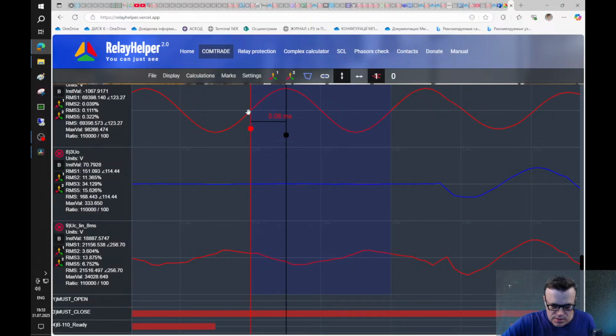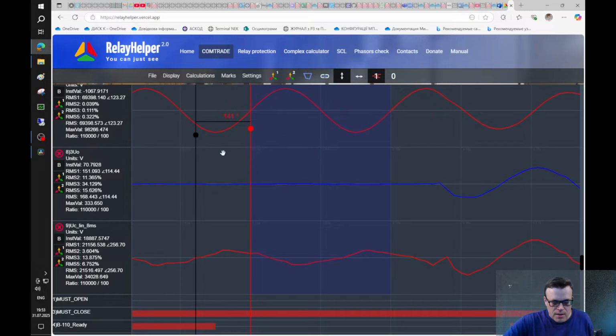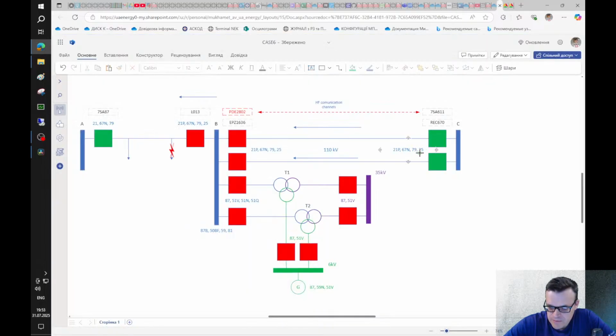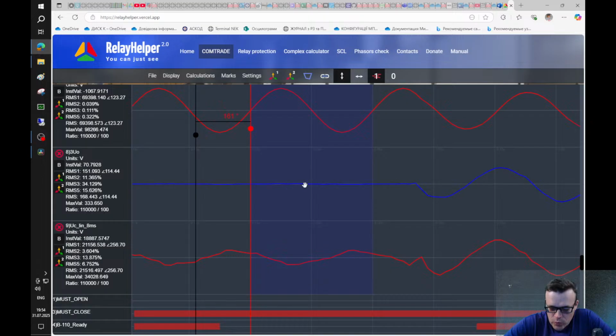Okay, here it started to grow, and here it also started to grow. So the difference is around 8 milliseconds, and we can convert to degrees, and the difference between these voltages is around 140 degrees. As I said, here we have the synchro check function. Why did we receive this reclosing? Usually, and we also have this setting, the allowed difference between voltages is around 30 degrees. I believe this setting is pretty much the same in the whole world.